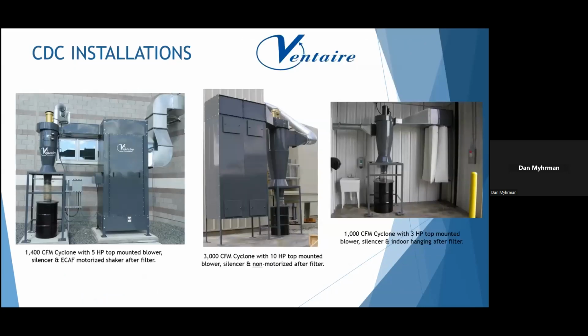A couple more pictures of some installed cyclones. This one on the left has another shaker. This one is actually basically just enclosed hanging filters, and they're manually cleaned and emptied. Basically, you have to go in there, shake them with a manual shaker bar, and the particulate will fall down to the bottom, and then that's where you empty it out. This is not recommended when you're returning the air back into the space.